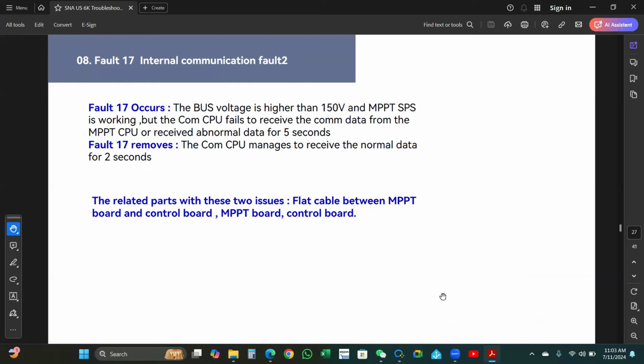Number 8, fault 17, internal communication fault 2. Fault 17 occurs when the bus voltage is higher than 150 volts and the MPPT SPS is working, but the COM CPU fails to receive the COM data from the MPPT CPU or receives abnormal data for 5 seconds. Fault 17 removes when the COM CPU manages to receive the normal data for 2 seconds.